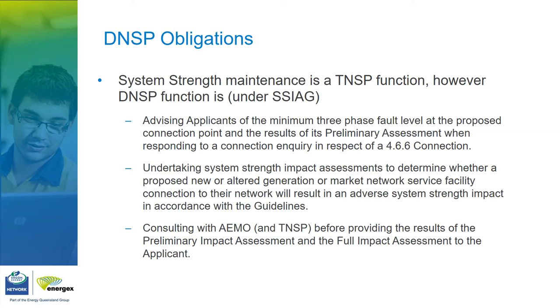So we need to be clear on what the DNSP system strength obligations are. In line with the system strength impact assessment guidelines and the system strength framework, system strength maintenance is a TNSP function. And under the SSIAG, our function is really to work with and advise applicants on aspects such as minimum fault levels, preliminary assessments, and undertaking system strength impact assessments. So this means it is very important for DNSPs to work closely with the relevant TNSPs and AEMO to ensure appropriate information and results are shared to properly assess system strength impacts and develop a path forward for proponents. But while there is a clear segregation of roles, the difficulty is around the system strength assessments, because there are no clear electrical physical boundaries for system strength. And that's why consultation between the NSPs and AEMO is critical to ensure there is an efficient connection process.